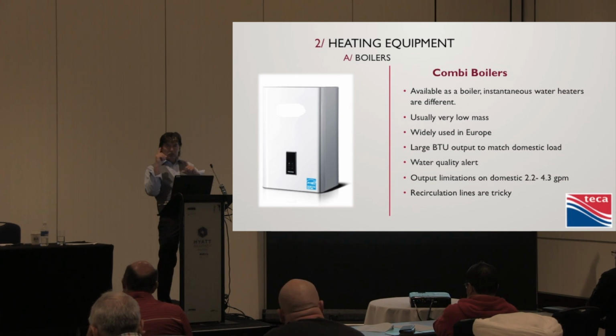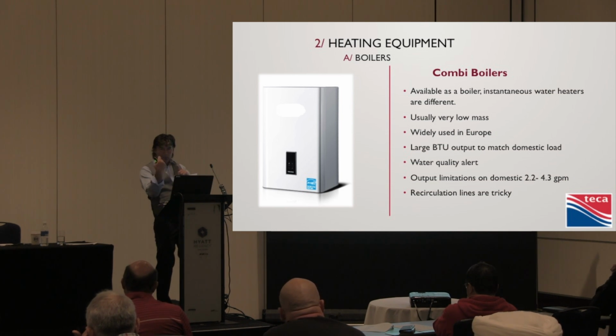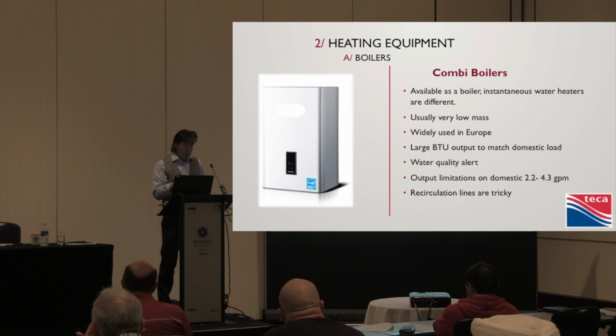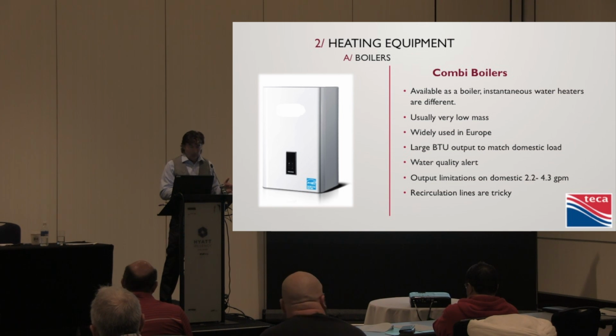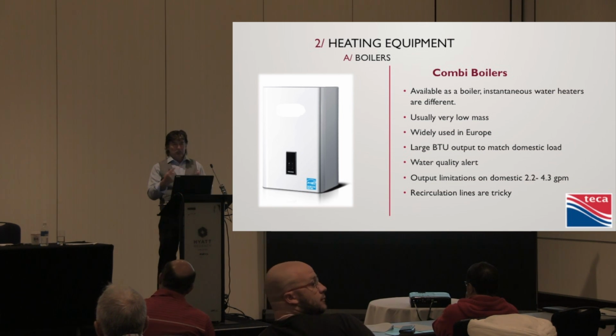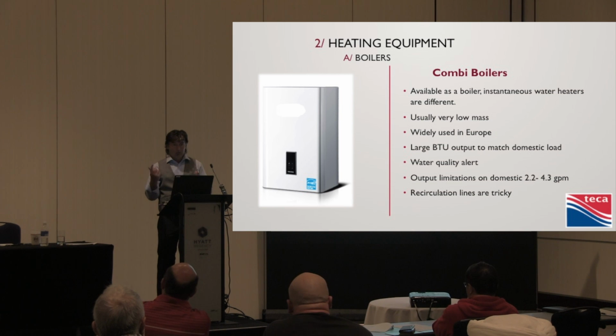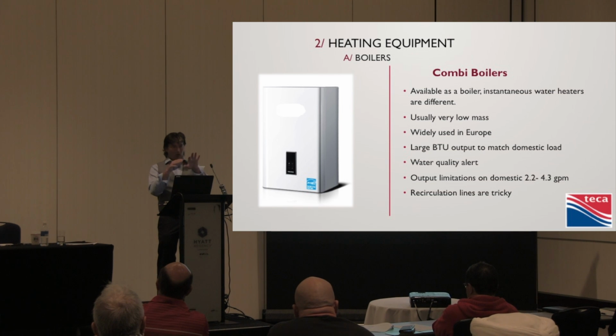So now if you take a recirculation line, run it all the way to the end, put a pump on it, and you tie it back into this heater, the whole point of instantaneous water heating is to have the thing shut off and not do anything when you're not heating water. So if we start recirculating, which I don't believe they do a lot of in Europe, now we're going to have this thing flowing through there all the time. So now the thing's waking up and going to flow, and so it's kind of on all the time.